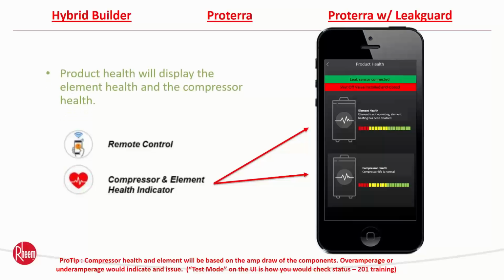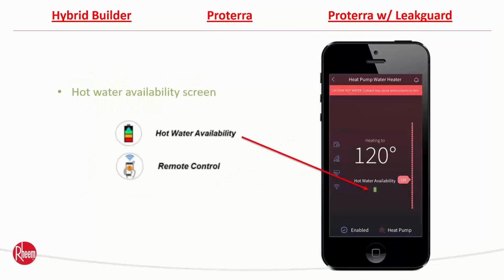With the hybrid builder, like I said, with the EcoNet, you're going to get some compressor health and element health. That's really going to help you with troubleshooting, or your contractor when he comes out to troubleshoot this thing. And if you go into test mode, you can actually see what that element and what that compressor are actually doing. You go into the hot water availability, like I said before. Now you can look at this. It's basically just like you see on your phone battery on your cell phone. That green box you see is either going to be full, 3/4, half, or down to 1/4. So you know how much hot water is in that tank.